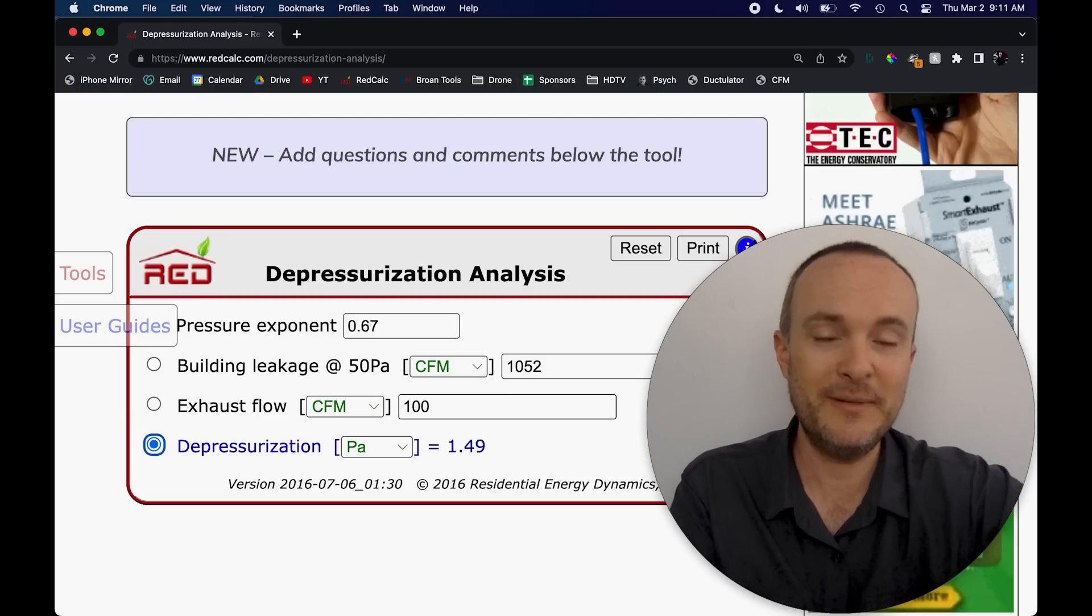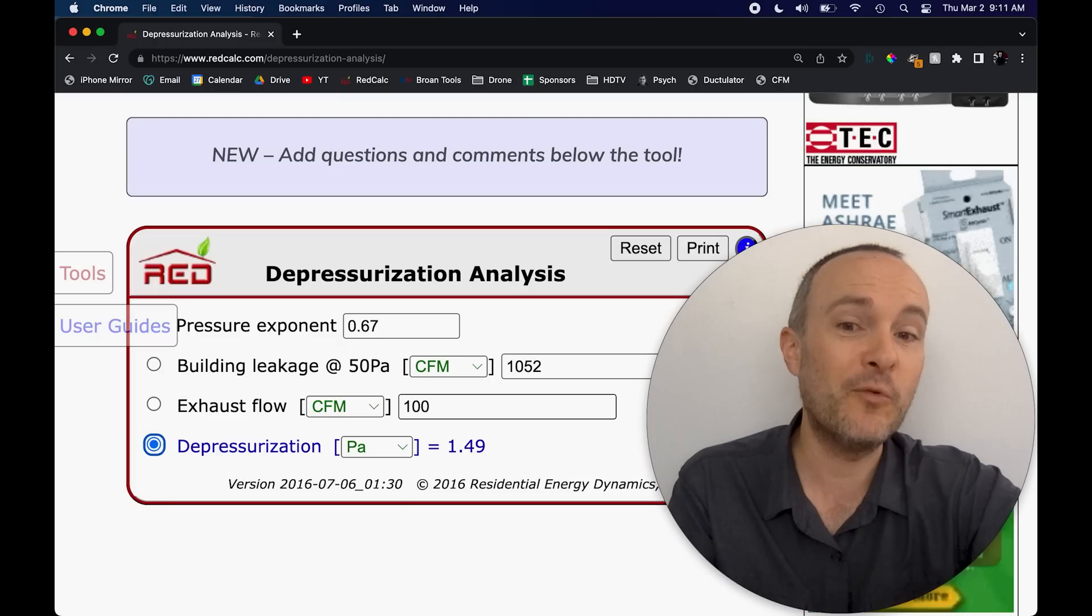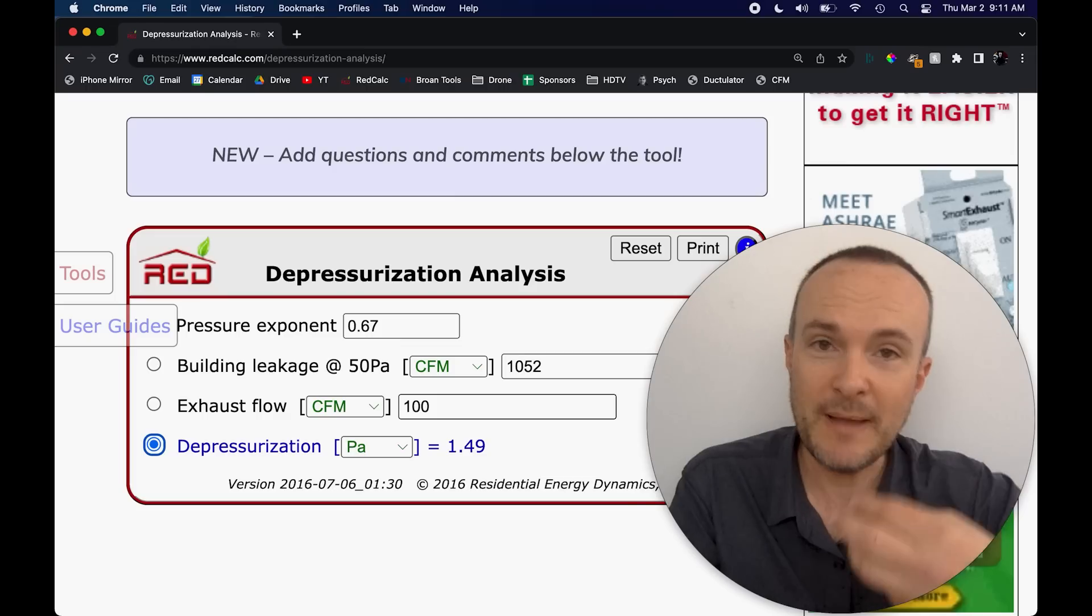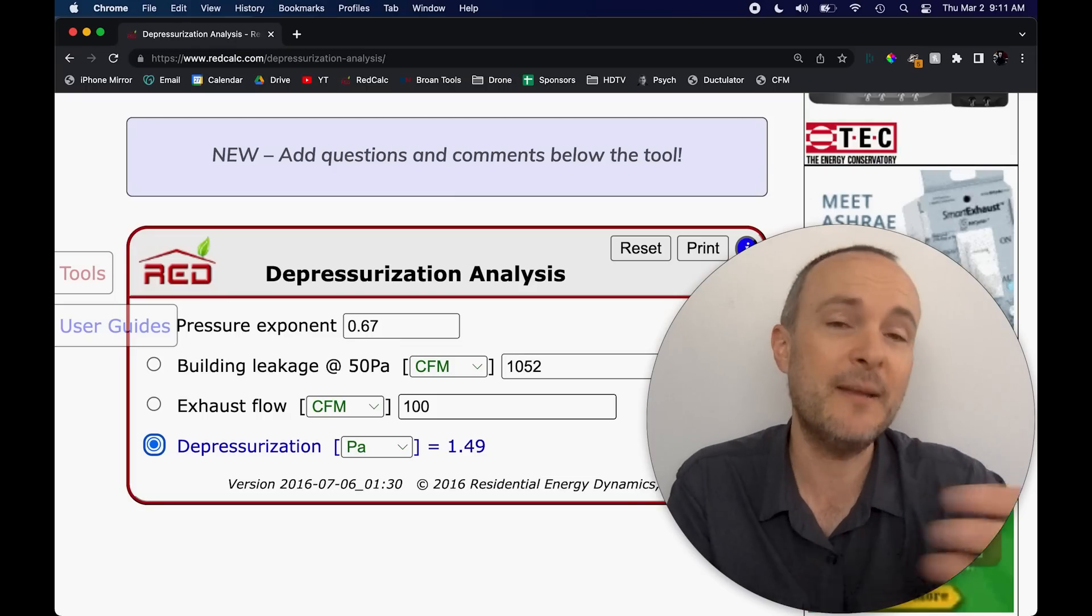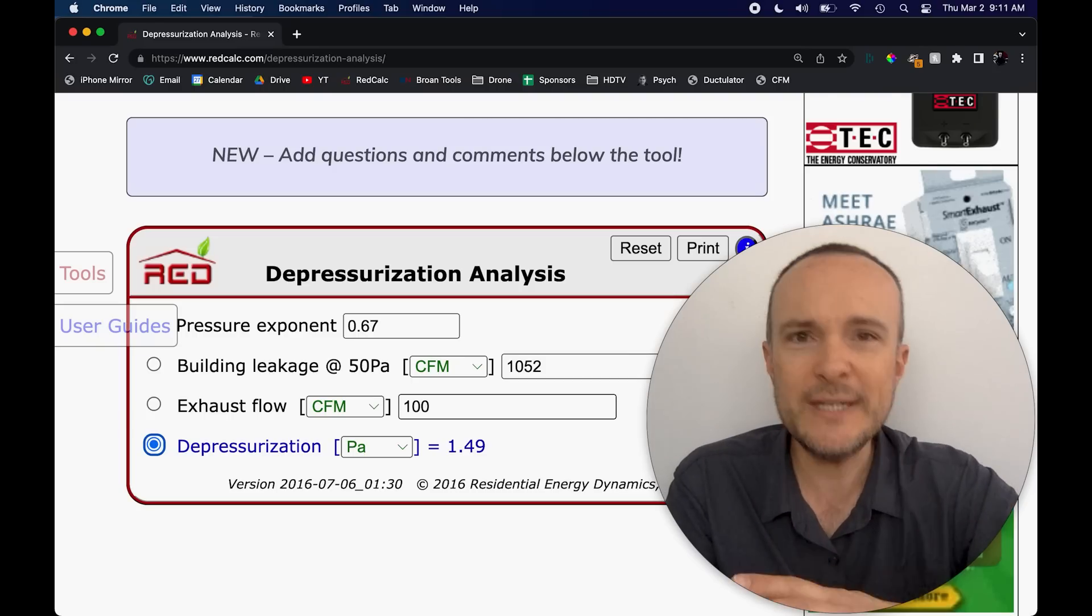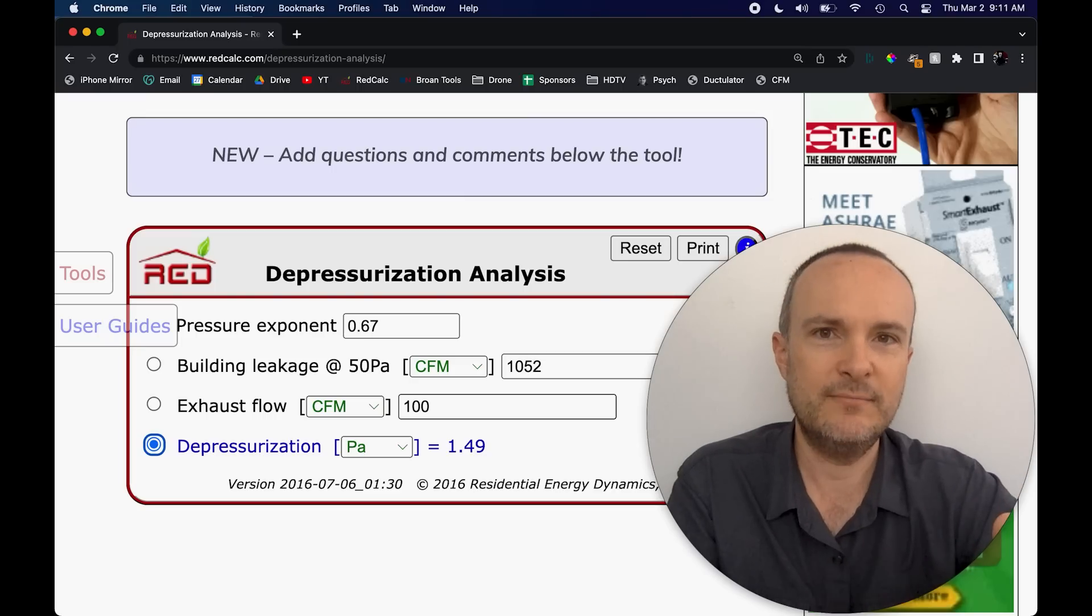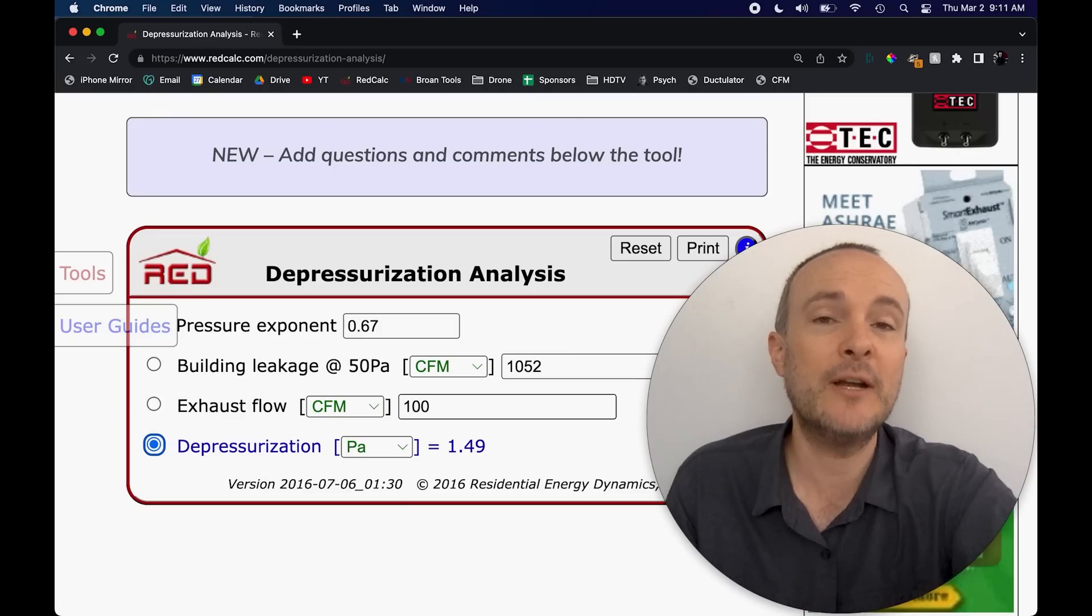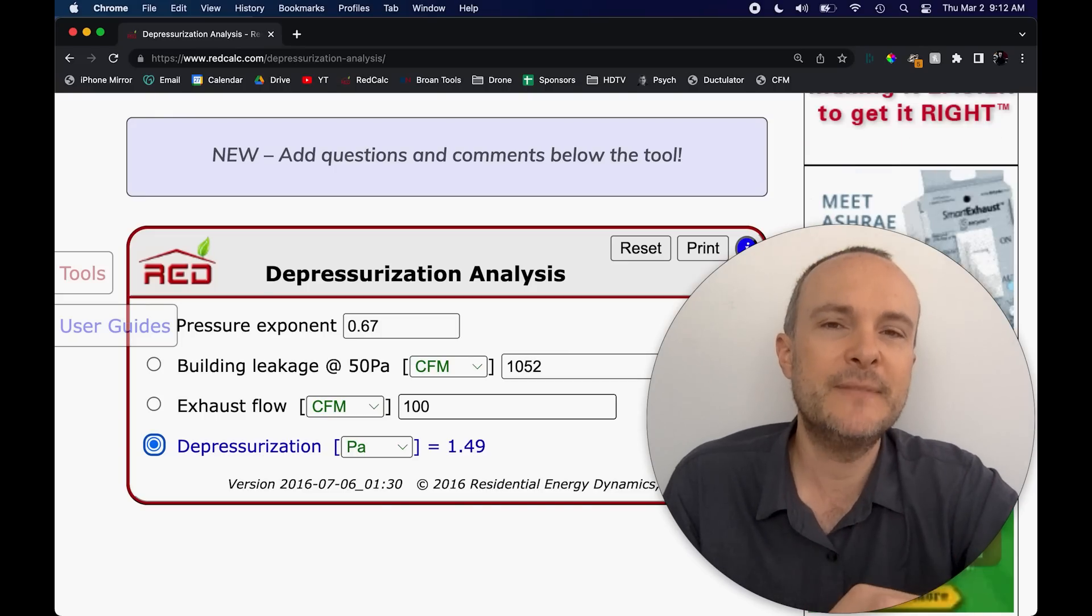Now I have had clients who have had problems with backdrafting chimneys at one and a half or two Pascals of depressurization consistently. So if you think it's likely that two exhaust fans are going to run and you have these elements in a home that have no business being in a 21st century home, like open hearth fireplaces, please don't do that. But if you have to, this is now we're nearing that line where it's probably likely that we are going to be sucking stuff down the chimney and we're going to be smelling the chimney. And now all of the things that we did to try to make this house airtight, which are a lot about health. Once you pass three ACH 50, you get tighter than that, the energy that you're saving is probably less important. Also, once you pass three ACH 50, the sizing of your HVAC in the manual J is going to have a less serious effect.